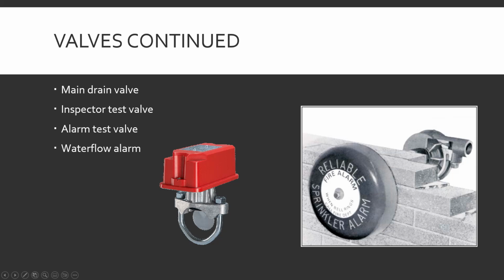Water flow alarms. This is a modern one. This is an old school one. Talk about the more modern one first, just because, kind of disappointingly, at least to me, these are the ones you're going to probably run into more often. Now, this sits in the pipe. There's this little flapper valve right here, a little plate of metal. Normally, when the system is all closed, everything's good, water's not flowing anywhere. So this is just sitting there. Little box goes, not moving, everything's cool.